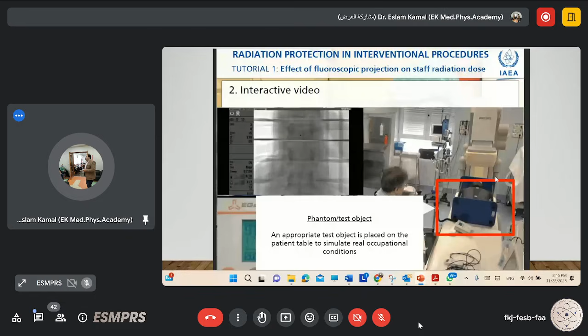As you can see in this video, we are going to measure the scattered radiation coming out from our patient during the fluoroscopic procedure. Now, if you put the X-ray tube down the table, this is our patient. We are going to compare the X-ray tube position down, top, and lateral, to see which position is good for dose exposure reduction. Here, if the X-ray tube is down, you will get 97 microsievert. If you move the X-ray tube to a lateral position and the detector is beside the image intensifier, you will get around 390 microsievert per hour.